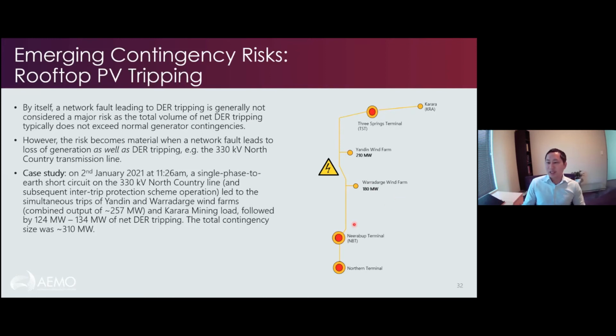So we had a single-phase earth fault on this line. And if you have a fault anywhere on this line, this whole line intertrips, and you take out all these generators. And so we had a combined output of 257 megawatts from these generators tripped. The Karara mining load trip, so that was a good thing. But then it was followed by 124 to 134 megawatts of rooftop PV inverters tripping. So the contingency size was 310 megawatts in total, roughly.